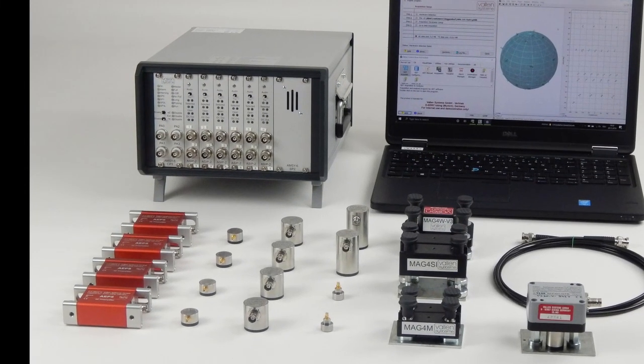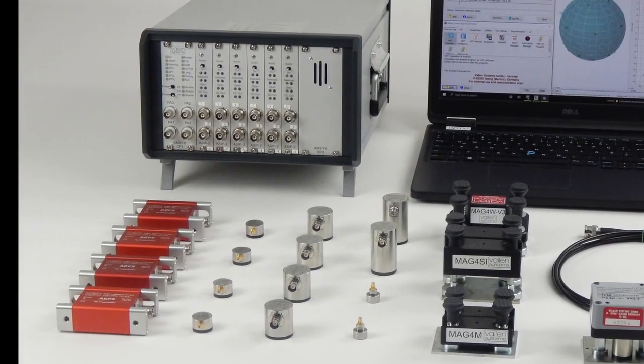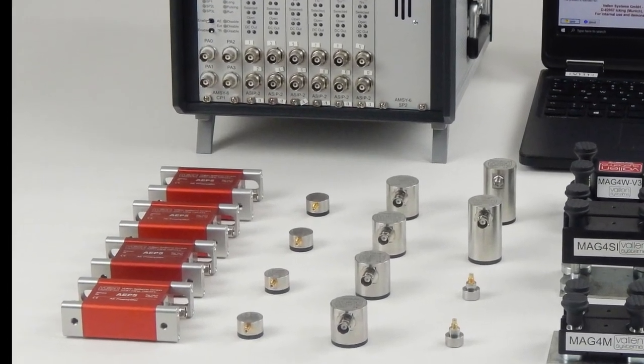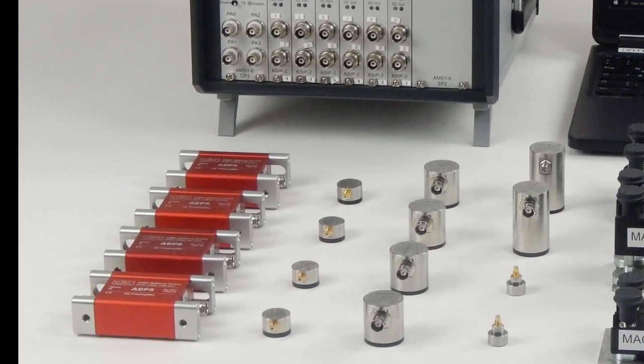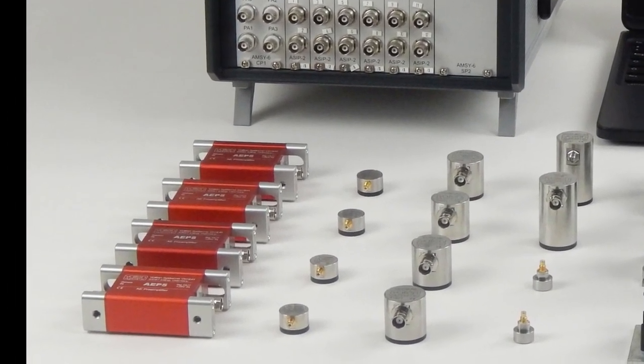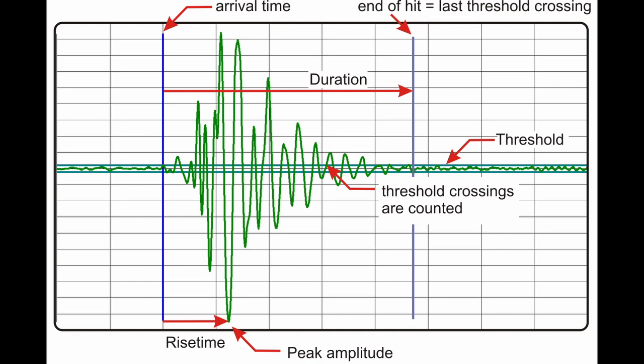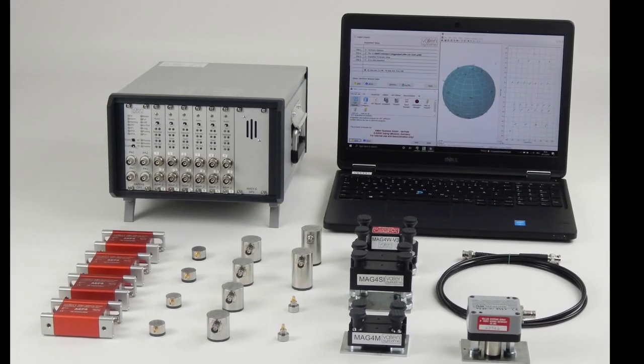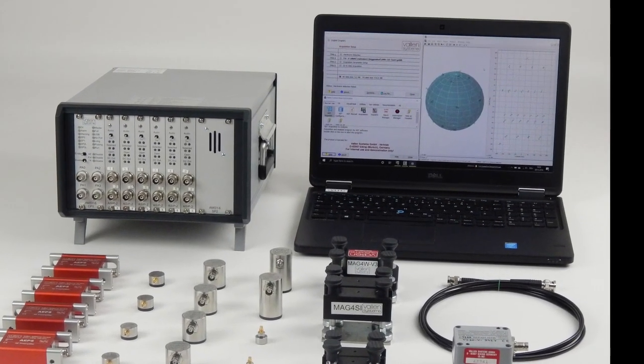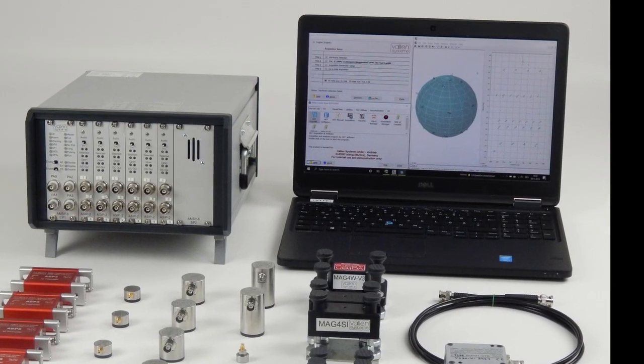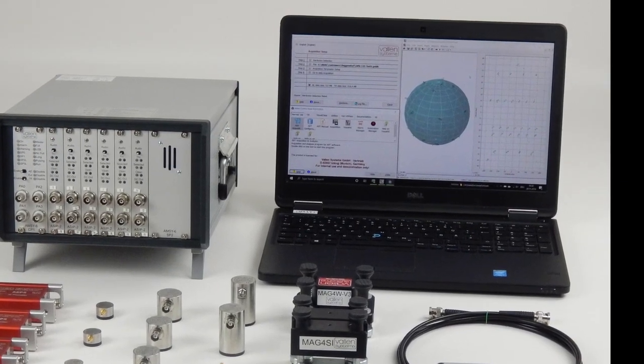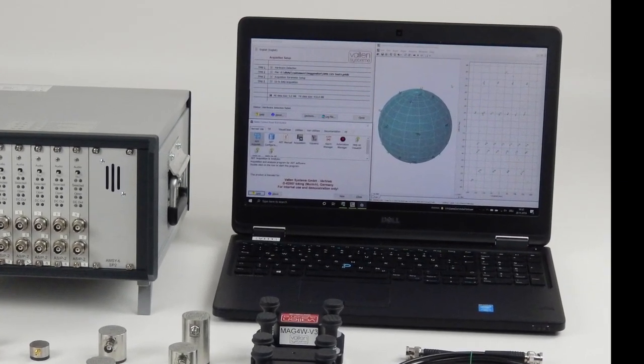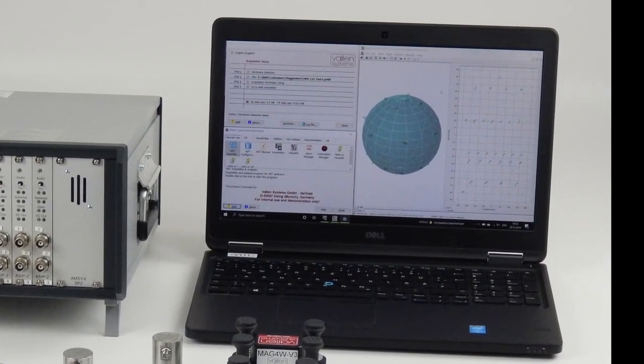A sensor converts a surface motion that is caused by sound propagating through the structure into an electrical signal. A preamplifier is used to amplify the sensor signal and make it immune to EMI. The data acquisition system conditions the signal and processes it. By doing so, it extracts specific features from a burst signal that is suitable for describing and characterizing it.